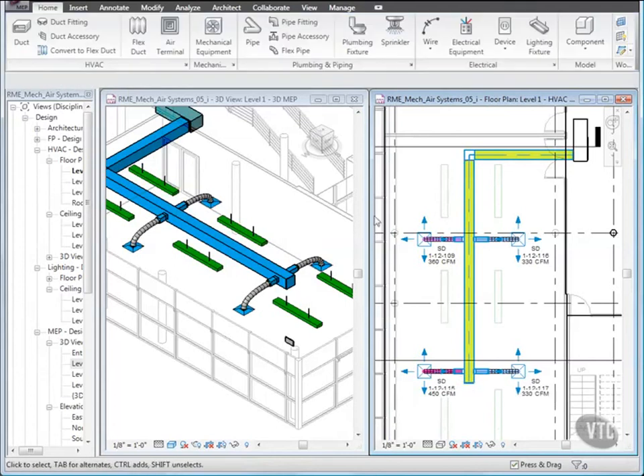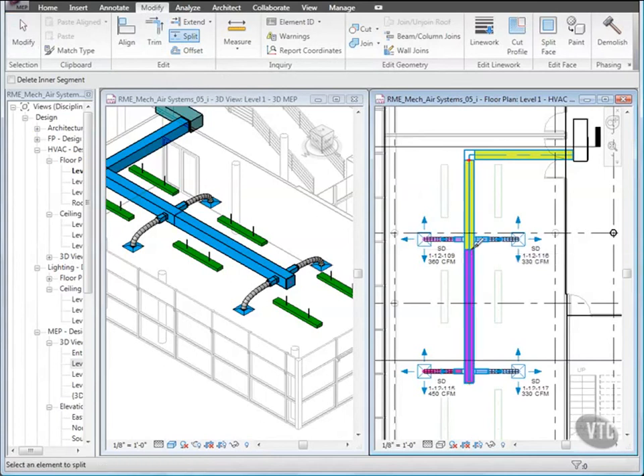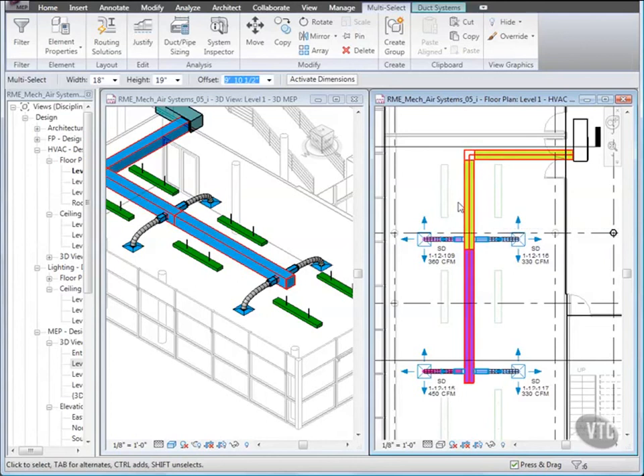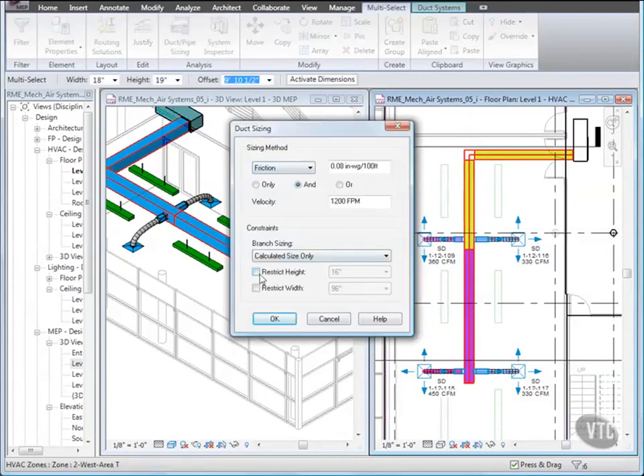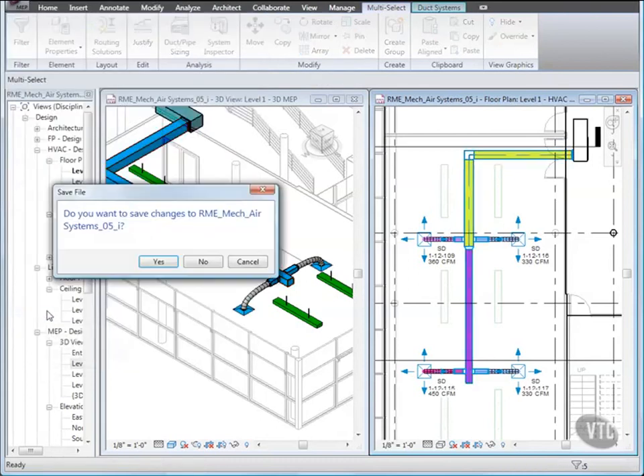Next, click the Modify tab, and from the Edit panel, click Split. Then click on the main duct below the top set of diffusers as shown. Click Modify. Then place your cursor on a section of the main duct and press Tab to highlight the entire main duct run, and click to select it. Then click Duct/Pipe Sizing, and make sure that Restrict Height is cleared, and click OK. When you do, the ductwork is sized to provide the appropriate CFM value for the system. The height constraint is used when you place duct in a restricted space, such as a plenum. Then close the file without saving it, as the next lesson will provide its own training file. And that concludes this lesson.